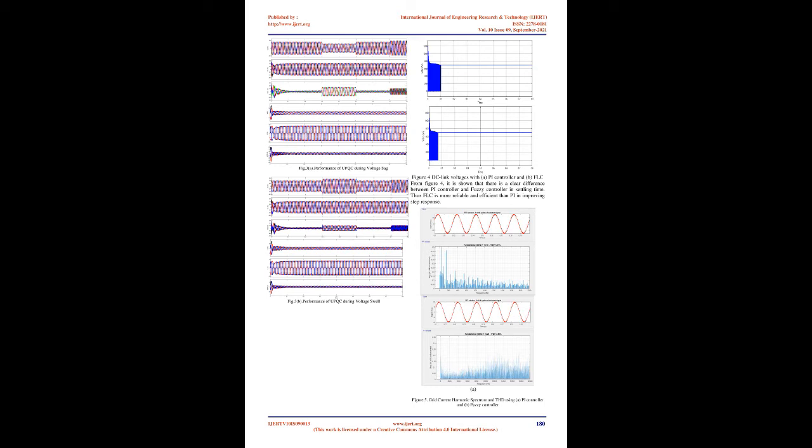Control of series compensator. Pre-sag compensation is done by the series compensator, along with compensation for energy optimization and in-phase compensation. There are many strategies which are used for the compensation. Voltage of the same phase, which is the same as the grid voltage, is injected by the series compensator in this project. This leads to minimal voltage injection. The figure below shows the series compensator control structure.